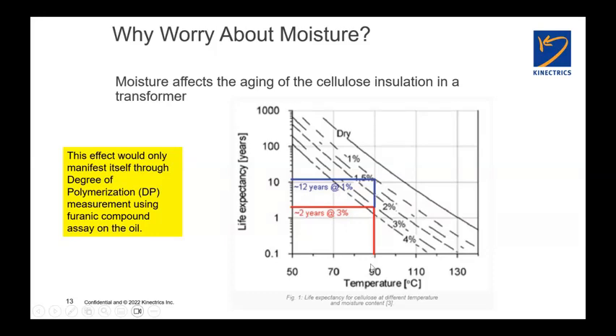And there's just an example. For a given operating temperature, in this case, I've picked 90 degrees C, not an unusual temperature for a fully loaded transformer. If you've got 1% moisture content in the paper, you could say that the lifespan of the paper insulation is going to be about 12 years. Increase that moisture content to 3%, so 3 times the moisture content, you'll notice that the lifespan of the insulation drops by a factor of 6, from 12 years down to 2. So it's not linear, it's a geometric progression.